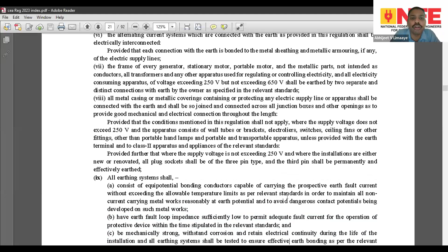Another development is the inclusion of fault loop impedance. Just before this we were talking about regulation 18, where it is mandatory for the supply agency to have its own earth terminal. Earlier we were using the terminology of earth resistance. However, earth resistance tends to get affected by how strong the supplier's earth grid is. So earth resistance becomes the responsibility of the supplier, whereas fault loop impedance is something within the consumer premises, and it can be calculated by the consumer.